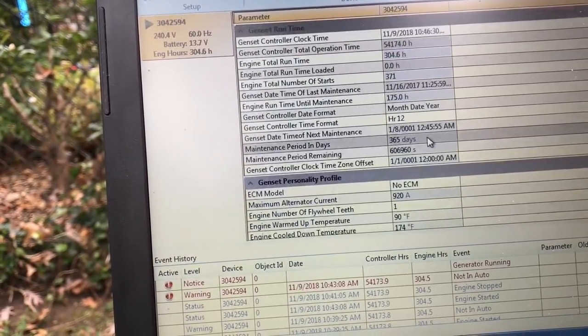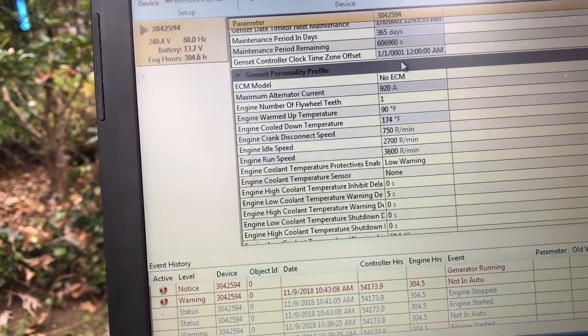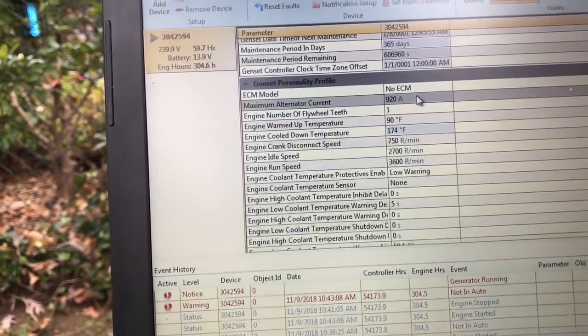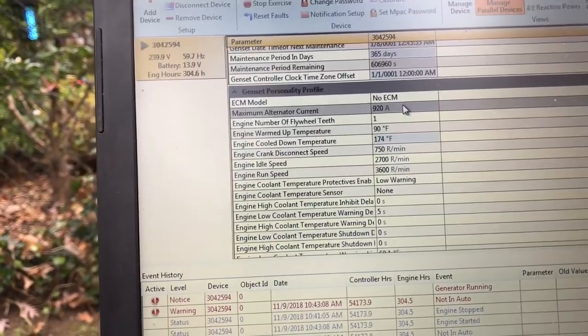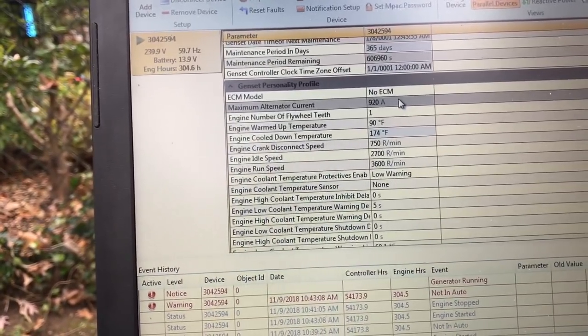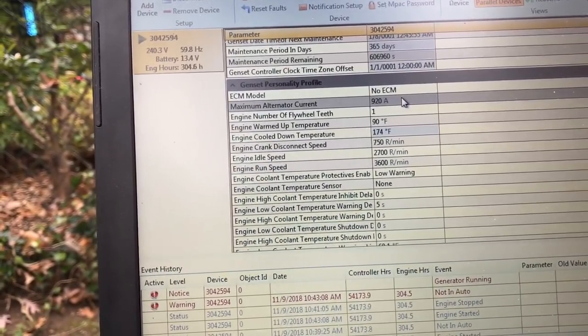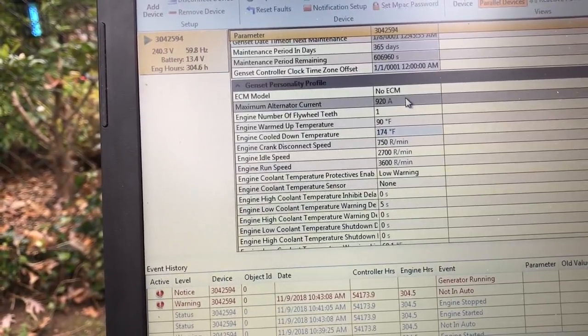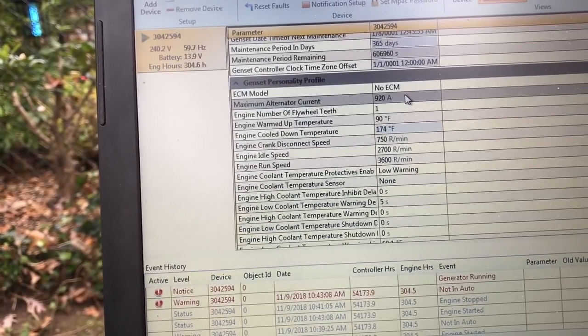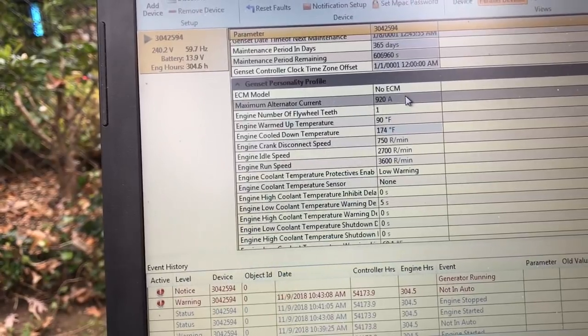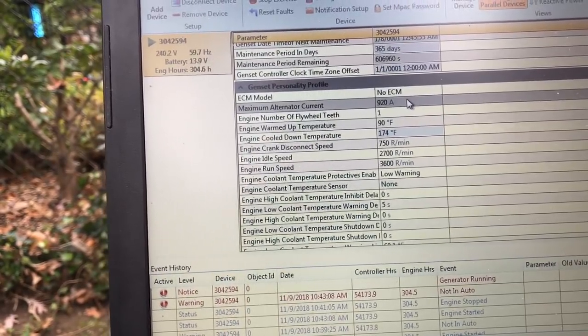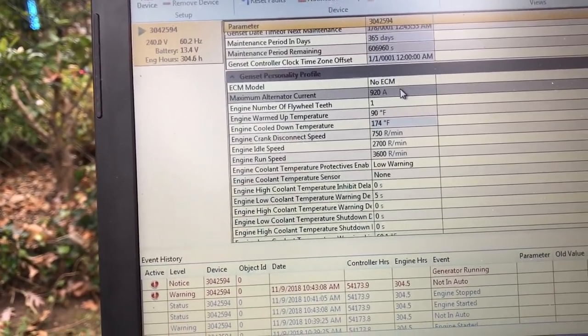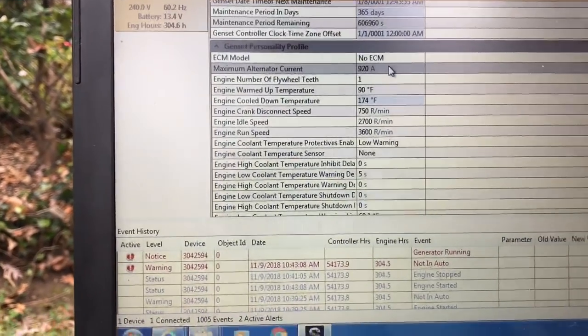Let's go down even more. My maximum alternator current, this is 920 amps. No way, there's no way I could handle that, but hey, that's what it's saying. Engine number of flywheel teeth, it's saying 1. Warm-up temperature is 90. Cool-down at 174, what that means is that at 174 degrees...